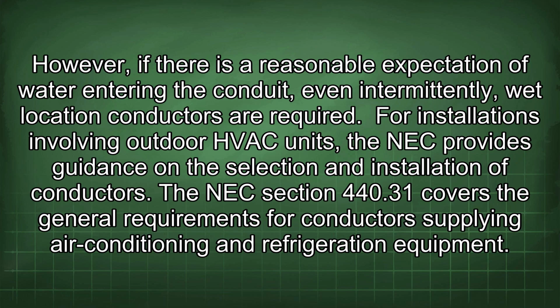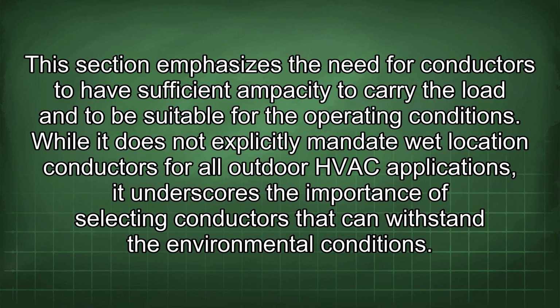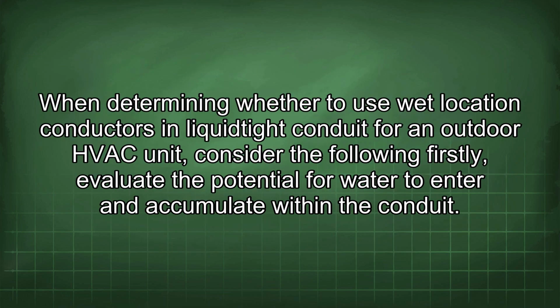For installations involving outdoor HVAC units, the NEC provides guidance on the selection and installation of conductors. The NEC Section 440.31 covers the general requirements for conductors supplying air conditioning and refrigeration equipment. This section emphasizes the need for conductors to have sufficient ampacity to carry the load and to be suitable for the operating conditions. While it does not explicitly mandate wet location conductors for all outdoor HVAC applications, it underscores the importance of selecting conductors that can withstand the environmental conditions. When determining whether to use wet location conductors in Liquidtight conduit for an outdoor HVAC unit, consider the following.